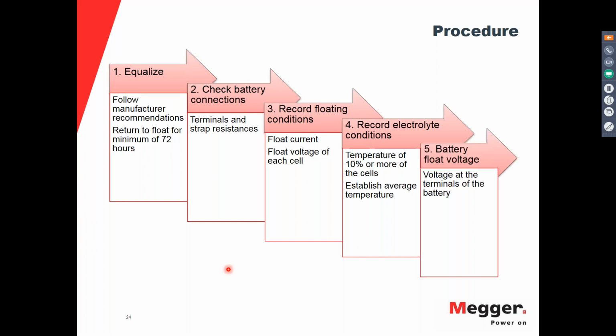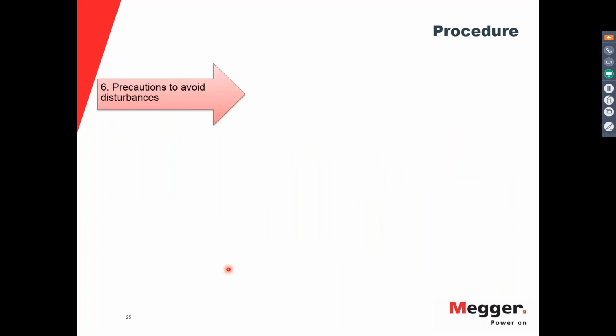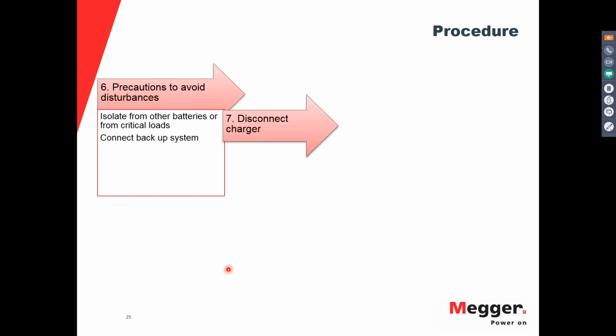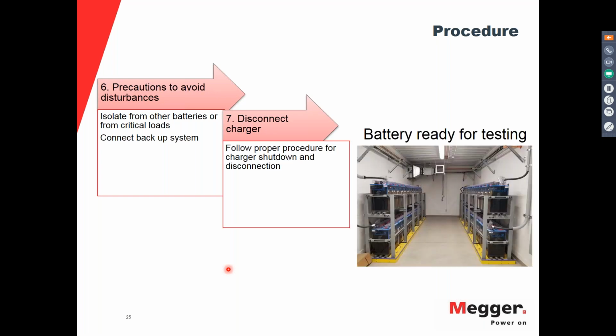Then measure the battery float voltage. Before, in step number three, it was the float voltage of each cell. You also want to measure the float voltage of the entire string at the terminals of the battery. And then you start getting ready to disconnect the charger and, if you are connecting a backup, this is the moment that you do that. You take all the precautions to avoid any disconnection of critical loads, and you follow all your internal procedures to avoid any problem with the system. At this point, you can disconnect the charger and connect the instrument to perform the test, and the battery is ready for testing.